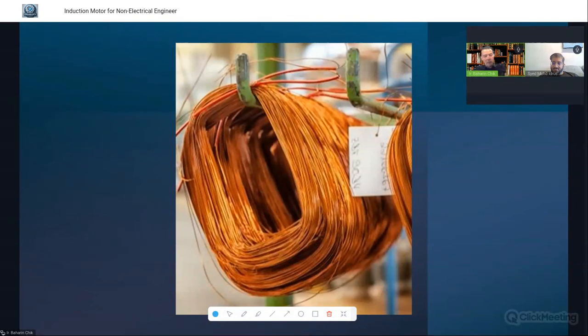But to answer this question, two pole motors run faster than four pole motors. So for us, it depends on the vendor. It depends on the application of the plant, whether you need a higher RPM or lower RPM. If they need the lower RPM, then we can go for four pole motors or less than that. But for the higher RPM, we have to go to two pole motors.